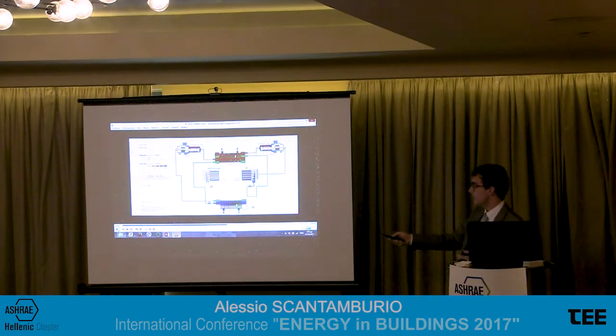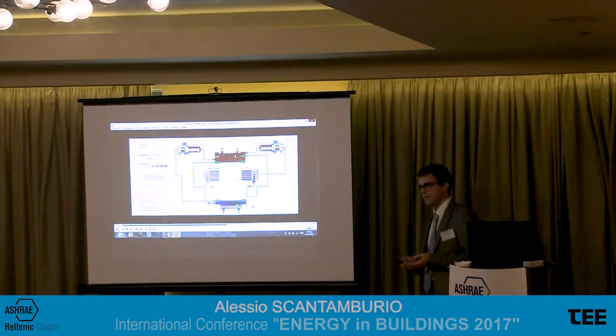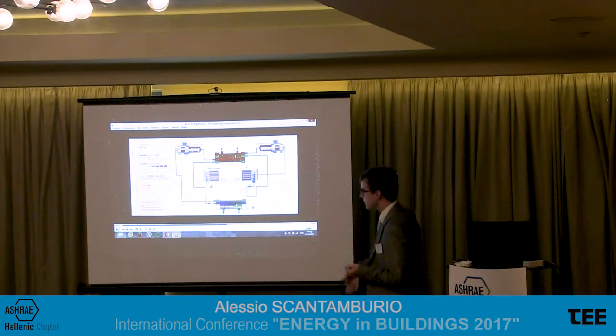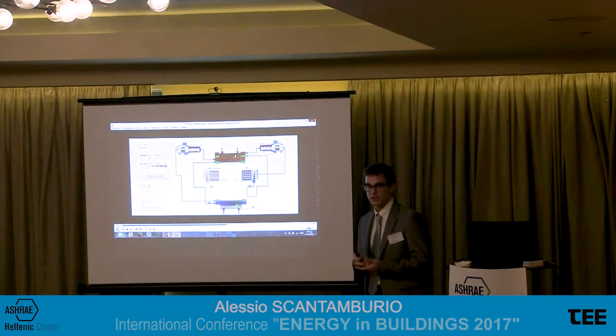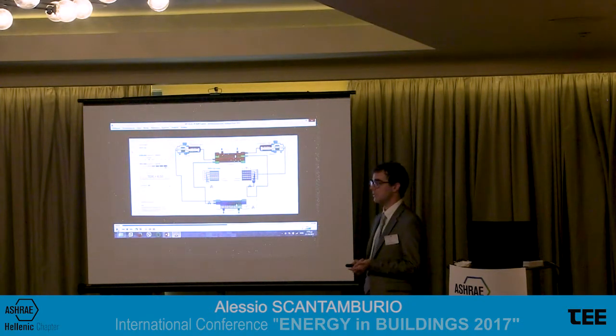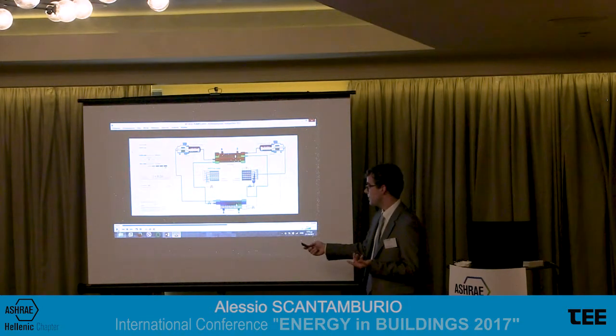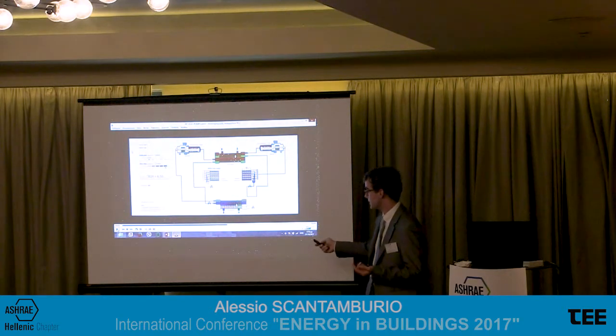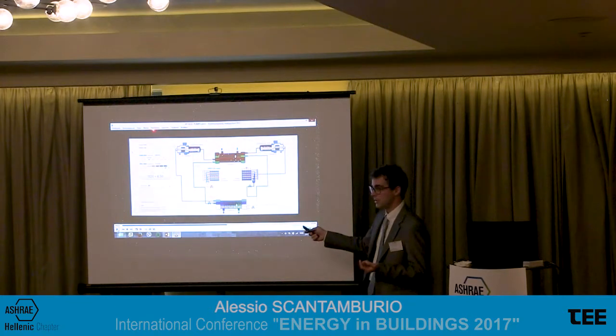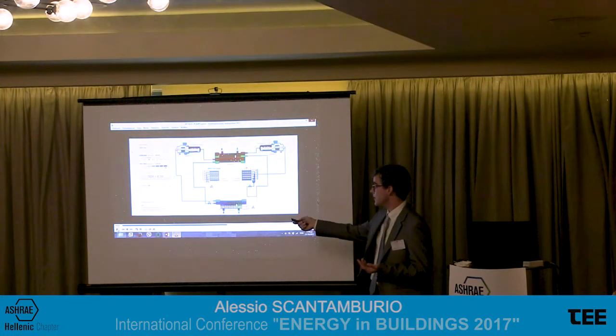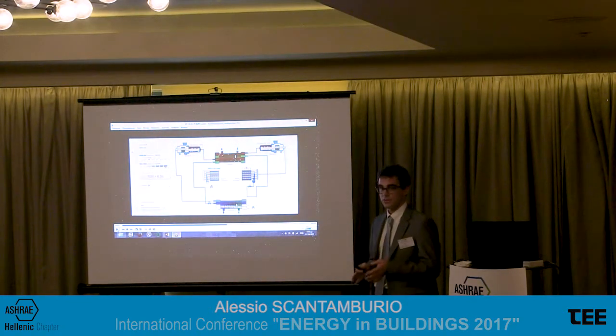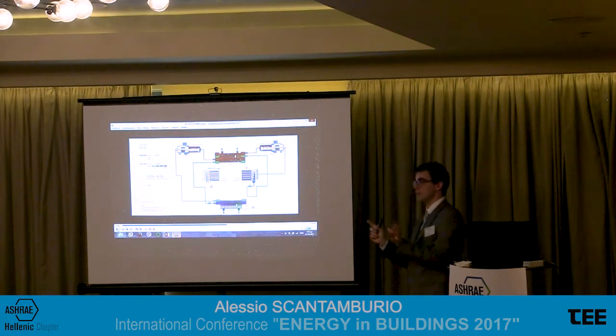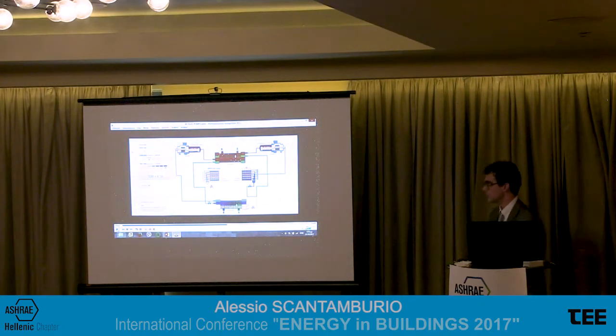You see here, we cannot measure the efficiency of this particular unit with the standard parameters like EER or COP we use in chillers and heat pumps, because in this case we must also take into account the fact that we have two useful effects. So TER, total efficiency ratio, is the sum of heating capacity and cooling capacity divided by the power input. And in this case, it can be really high, also over 8 in certain conditions, because we have two useful effects with one single power input.